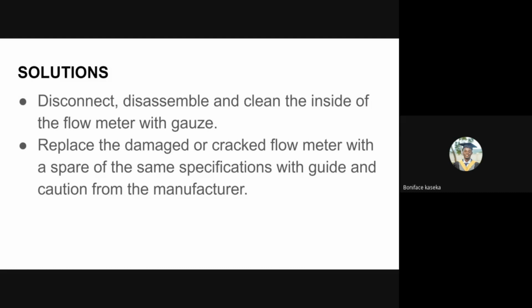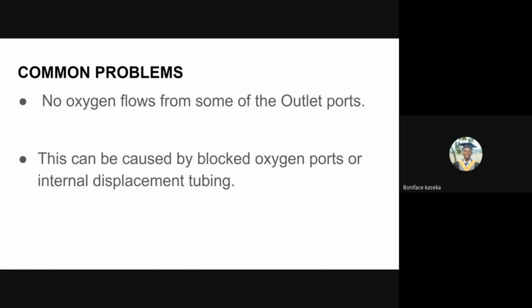So lastly, I'm going to talk about another problem that is very common as well. Sometimes oxygen flows from some of the outputs, but not from others. You can have two outlet ports which are not producing oxygen. This can be caused by blocked oxygen ports, or maybe there's an internal displacement of the tubing. Sometimes, due to dust and other debris, they may block the oxygen port. And that is also not good, because it means that you'll not be servicing as many patients as possible.